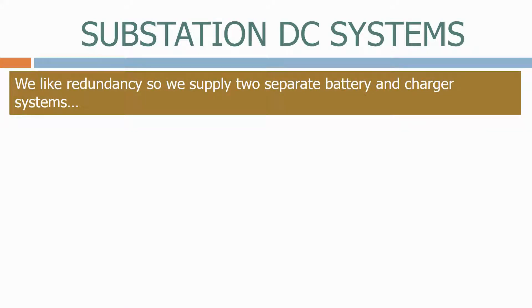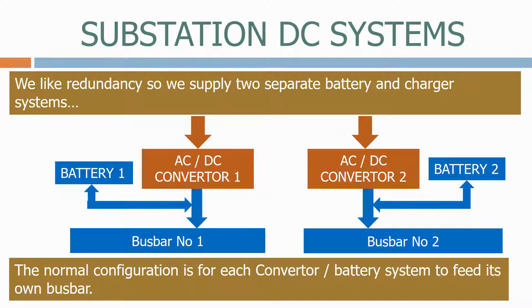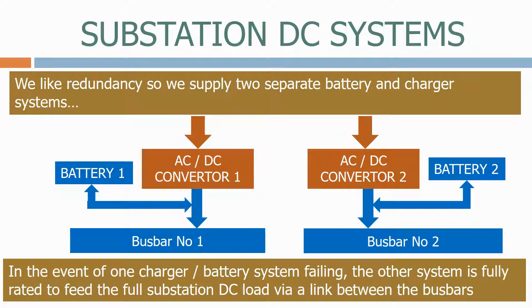We like redundancy, so we supply two separate battery and charger systems. These feed their own busbar and loads. The normal configuration is for each converter battery system to feed its own busbar. In the event of one charger or battery system failing, the other system is fully rated to feed the full substation DC load via the link between the busbars.